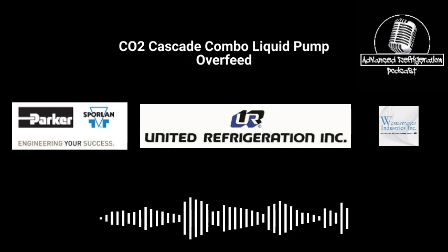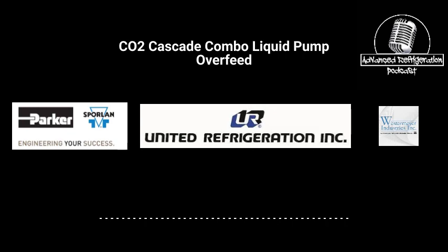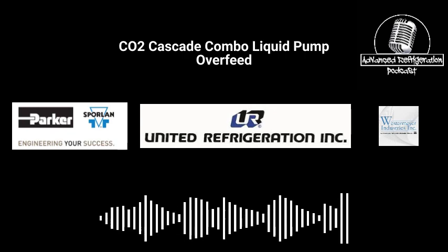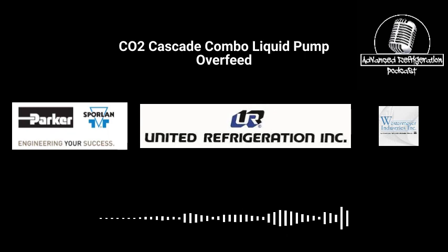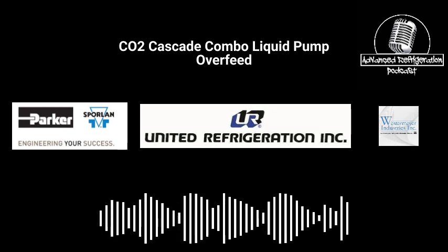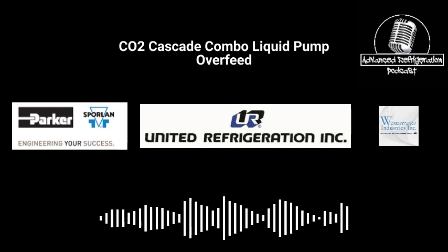I'm just saying. So here's my take on that. It's 2023. How is there not capacitor banks on valve drivers? Yeah, I don't know. But certain valve drivers do have it. Like the Emerson Dixel stuff, you could buy a capacitor bank, like a valve battery basically, for those to drive shut. I'm almost positive the Micro Thermo ones drive shut. The Beacon ones do. The QRC. Yeah, I'm almost positive the MT ones drive shut. I don't know. We're gonna have to ask Charlie. Yeah, but I know on the 700 boards you could buy a battery. There's a battery supply backup that goes on, at least on the rack boards, for that.